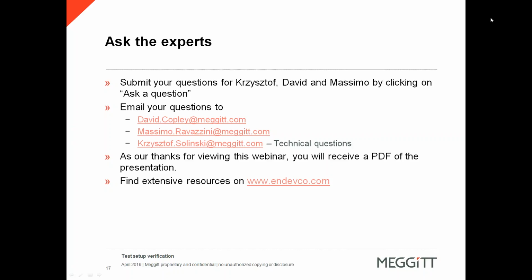And our last question from Matthias. According to the sensor output simulator 4830B specification, it can simulate single-ended voltage output. Can I use this single-ended voltage output to simulate differential voltage outputs? Well, the differential voltage amplifiers may feature a different internal construction, so I cannot provide a general yes or no answer to this question.